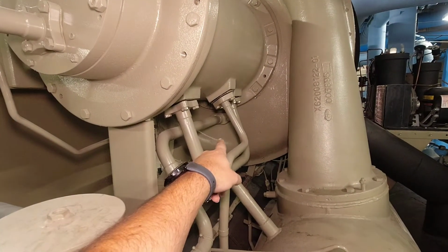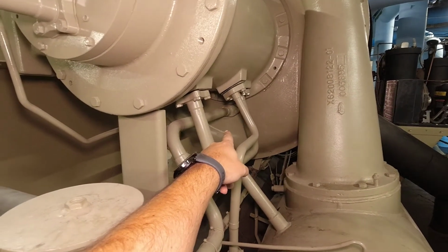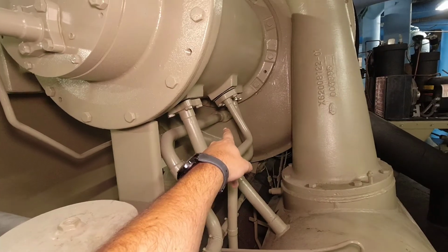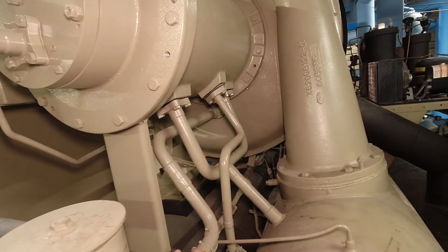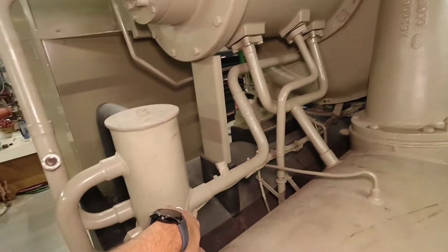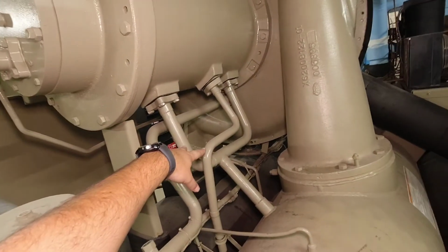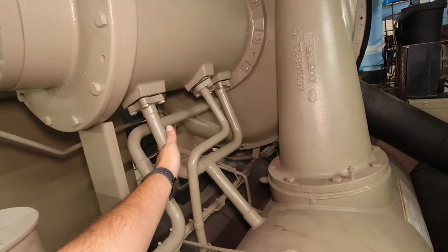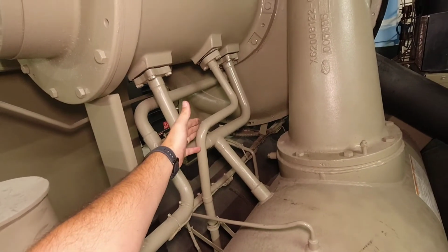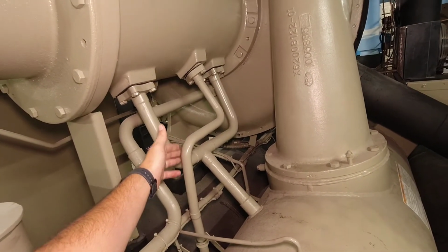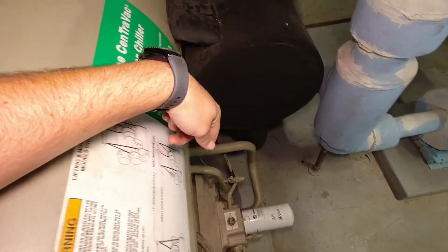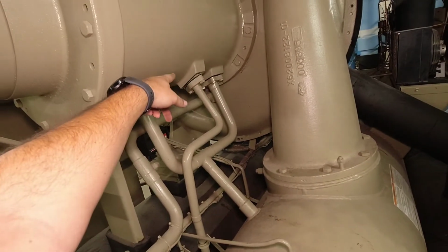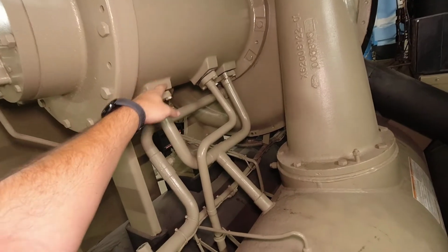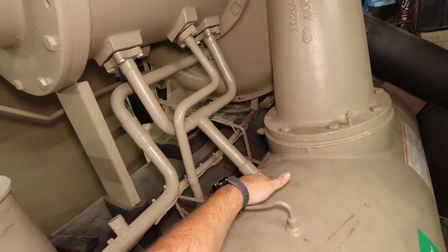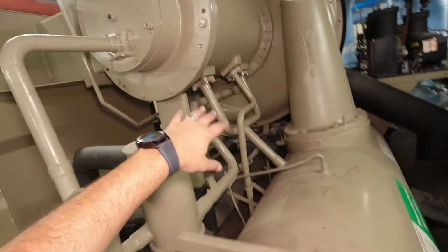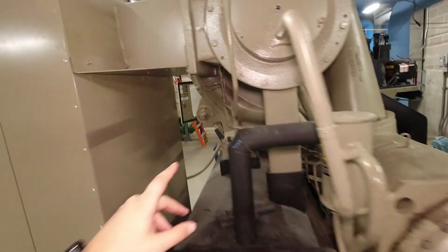That port there on the bottom of the scroll housing, underneath the motor, is the front bearing's oil return line coming back as well. These here are your motor cooling lines. This is coming off of your refrigerant pump down here off of the sump, and it's pumping the refrigerant in through a flash plate into the motor to help cool it, and then it returns back into the condenser. Again, that's just to help keep the motor's temperature stable.